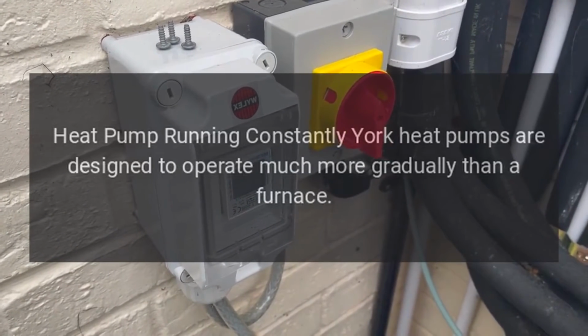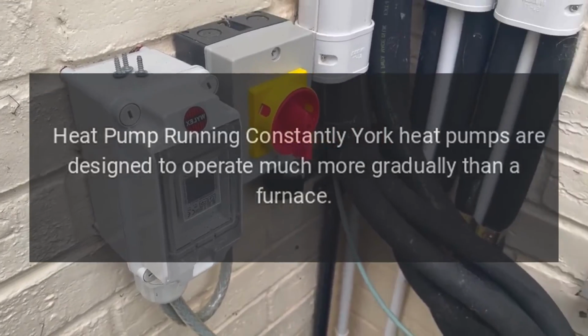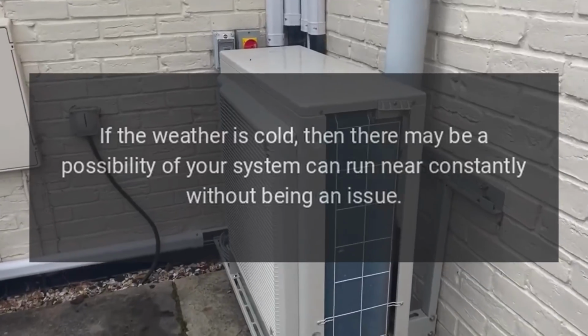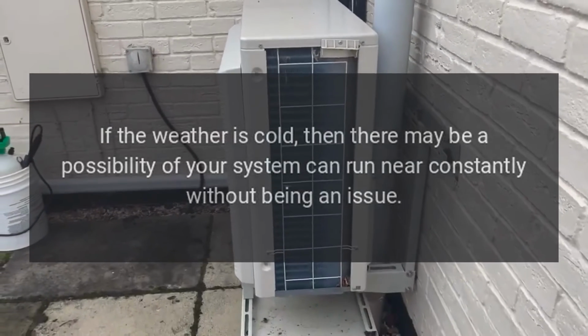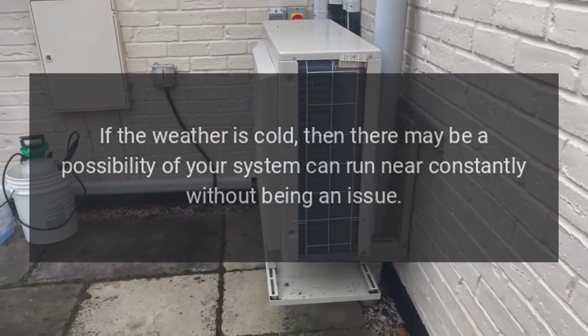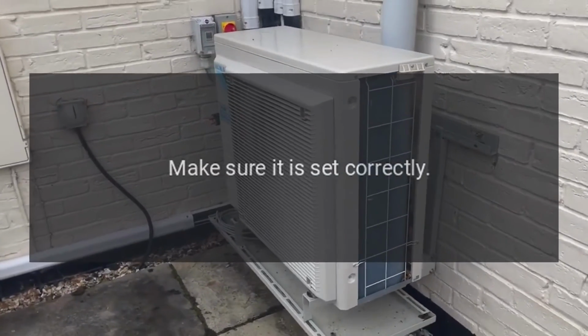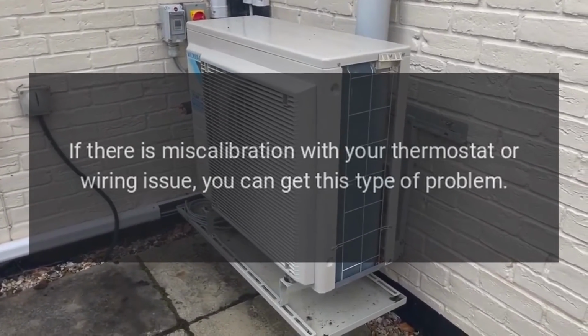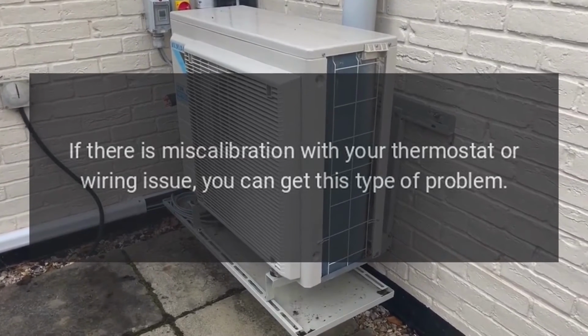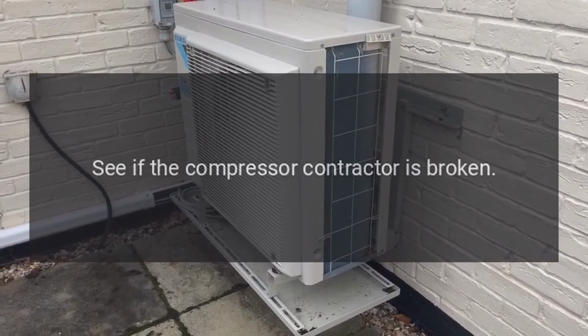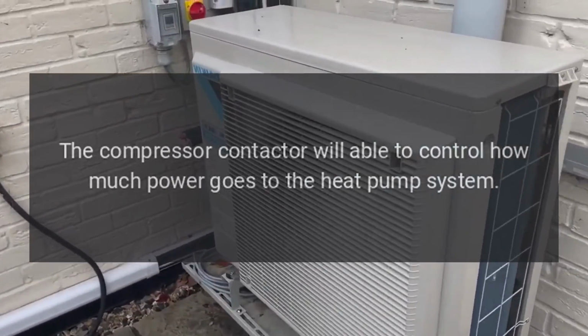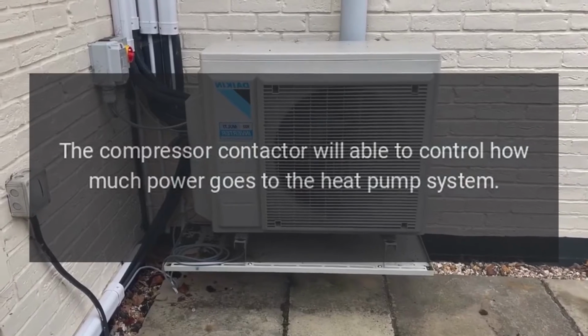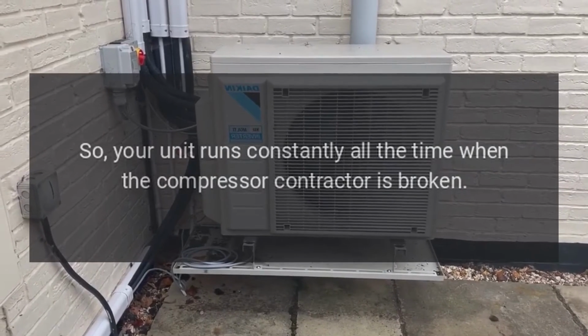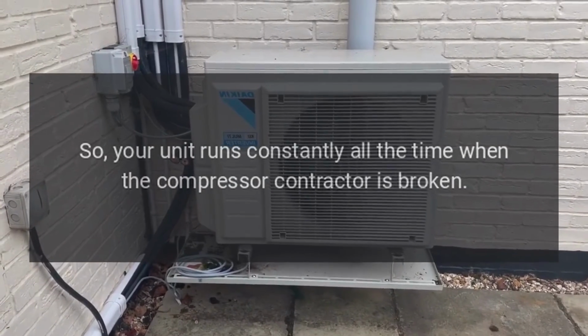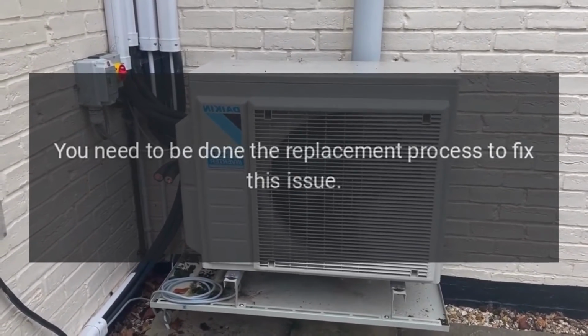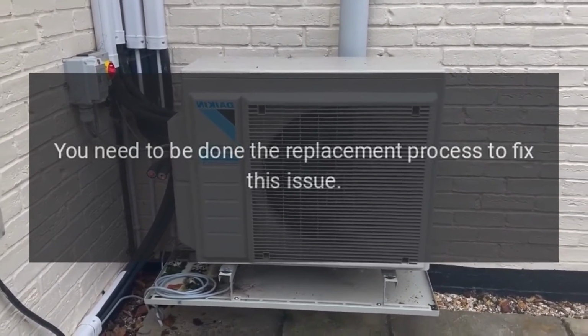Heat pump running constantly. York heat pumps are designed to operate much more gradually than a furnace. If the weather is cold, then your system may run near constantly without being an issue. Check the thermostat. Make sure it is set correctly. If there is miscalibration with your thermostat or a wiring issue, you can get this type of problem. See if the compressor contactor is broken. The compressor contactor controls how much power goes to the heat pump system. So, your unit runs constantly when the compressor contactor is broken. You need to do a replacement to fix this issue.